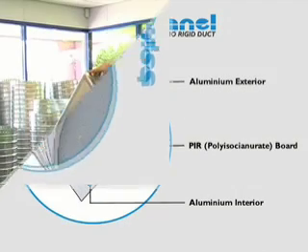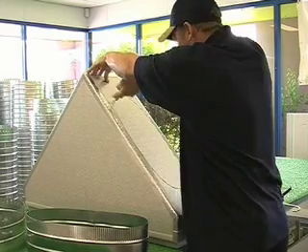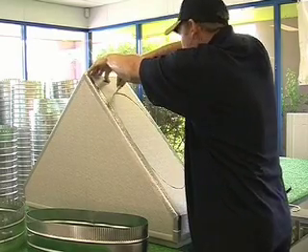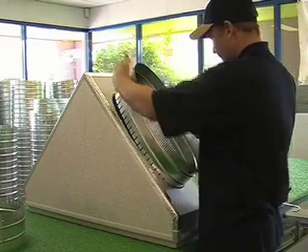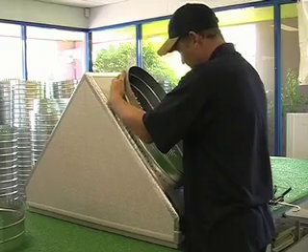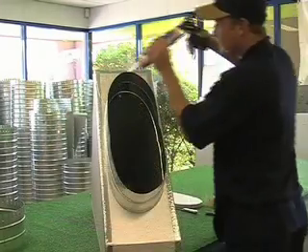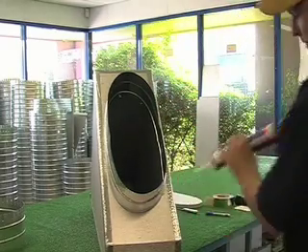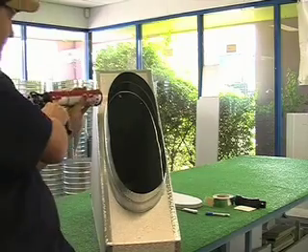within the duct. Construction of duct from Polypanel eliminates any thermal bridges, provides continuous insulation to all parts of the installation, greatly reduces the risk of condensation, is easy to clean and more hygienic, and all joints are sealed against air loss via glue, silicone and/or tapes. While the board is rigid and strong enough to support itself over reasonable lengths, it is easy to cut and mould.